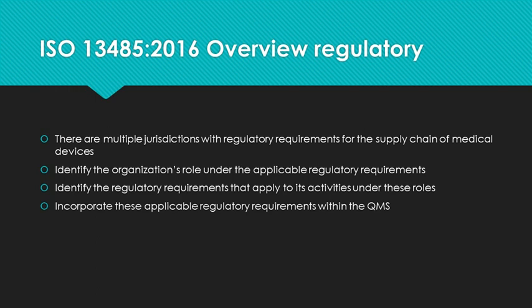There are multiple jurisdictions with regulatory requirements for the supply chain of medical devices. If you are looking at implementing ISO 13485, you must know if you need to comply with European standards or Australian regulations. Those companies implementing ISO 13485 are expected to identify the organization's role under the applicable regulatory requirement. So they need to know, are they the company that reports an incident, or are they up the supply chain and must report to their customer? They have to identify who is the regulatory authority — is it just the FDA, or do they also need to meet Health Canada?